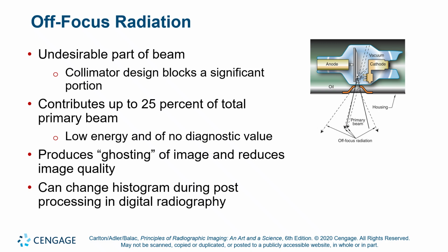And so these X-ray photons, like their electrons that spawned them, are heading off in unintended directions. And so we try to control like the escape route of the X-ray beam, but we're gambling on that the X-rays started from the focal spot. And so our apertures and our collimators are aligned to the focal spot. And so we can rein in the size of the beam from the photons that are created the right way. Any of the off-focus photons, the aperture and the collimator blades are not lined up appropriately to rein those in, and so we do get some off-focus radiation heading out of the X-ray tube and outside of the collimated field. Okay.